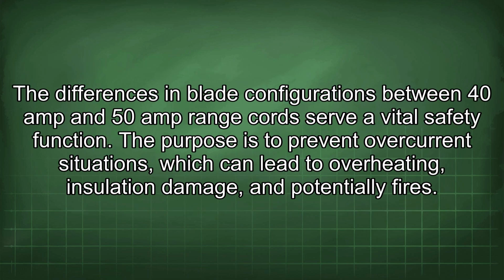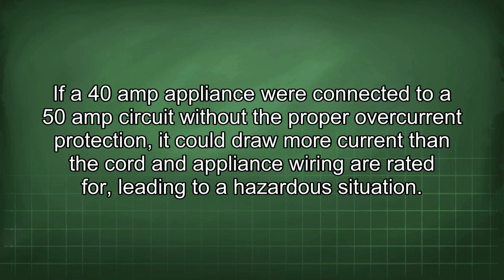The differences in blade configurations between 40 amp and 50 amp range cords serve a vital safety function. The purpose is to prevent overcurrent situations, which can lead to overheating, insulation damage, and potentially fires. If a 40 amp appliance were connected to a 50 amp circuit without the proper overcurrent protection, it could draw more current than the cord and appliance wiring are rated for, leading to a hazardous situation.